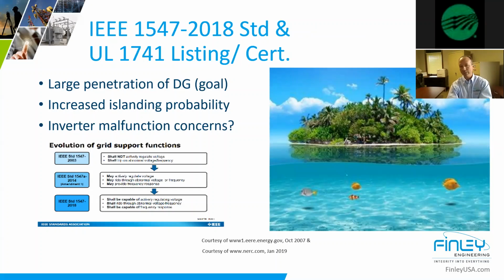What does this mean to you as the operator? Manufacturers are building devices to hang on. We're going to talk about fault ride-through theory here in just a few minutes because this is important to our discussion. Devices that used to trip quickly due to a fault occurrence are now trying to hang on because of power electronics - they've gotten so much better capacity and magnitude capability. They can hang on through a temporary fault, and some faults, and contribute to your total fault current.